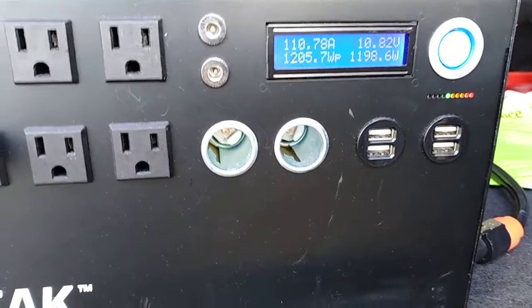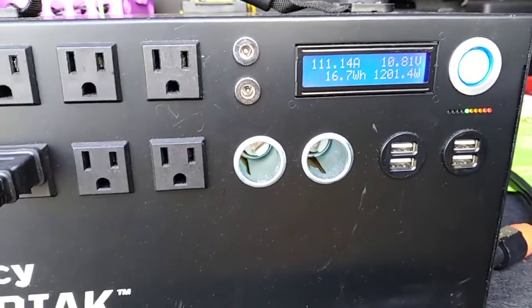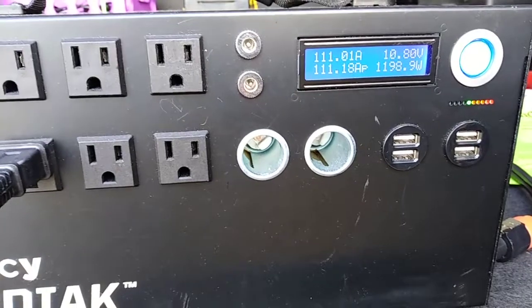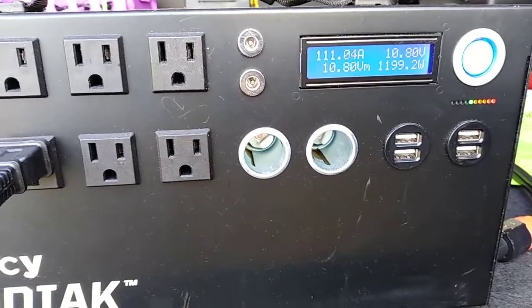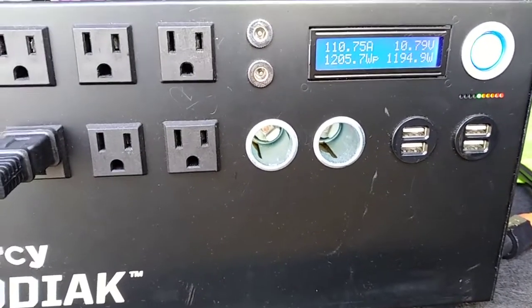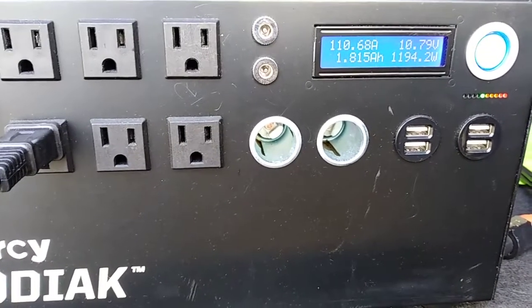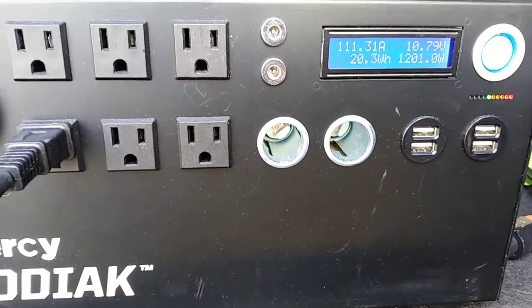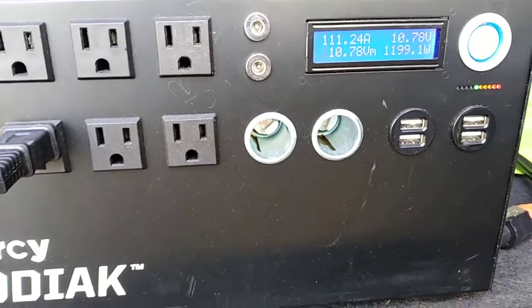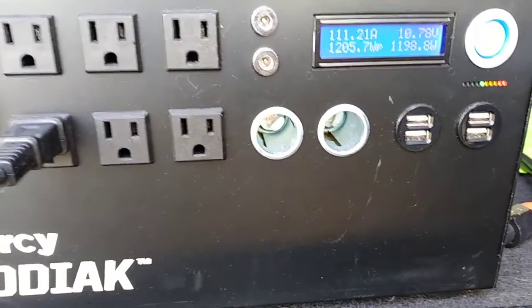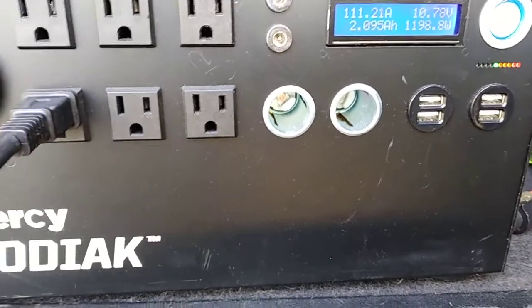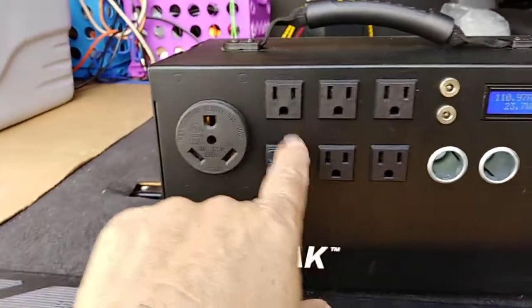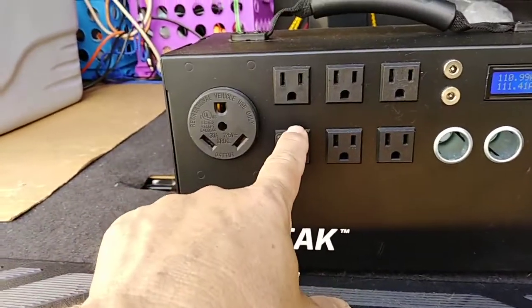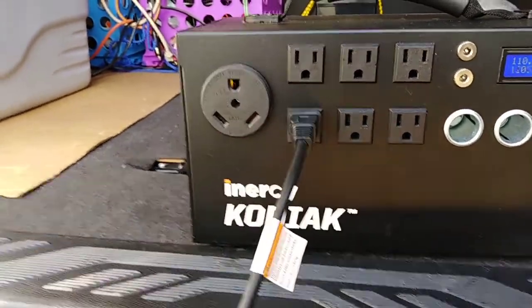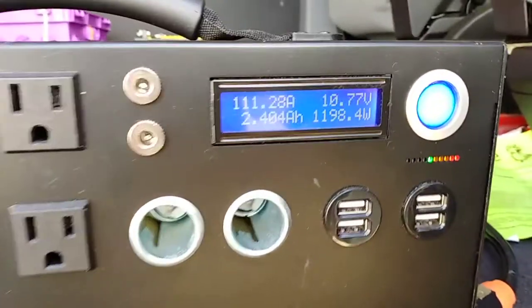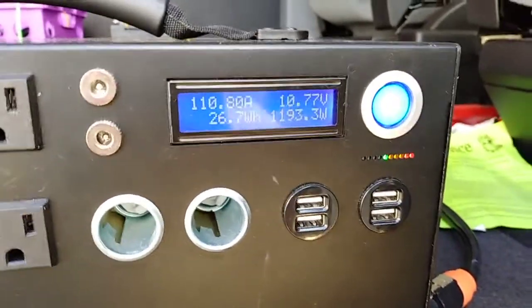This is the spec of the Kodiak. The Kodiak can surge up to... no, I take it back, it can surge to 1,500 watts. But a single receptacle running continuously is only rated for 1,000 watts, and I'm over it, roughly 200 over.